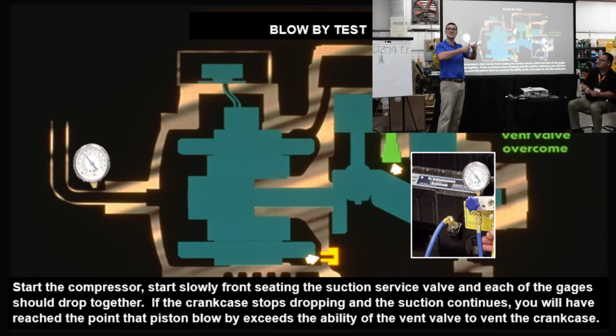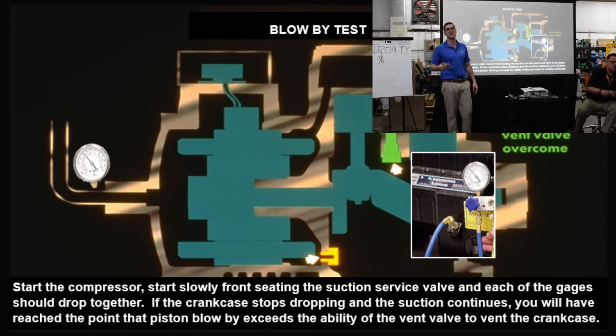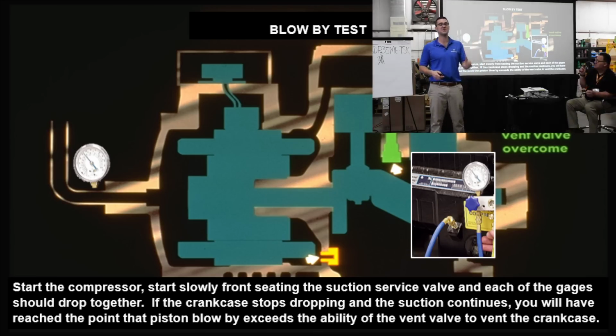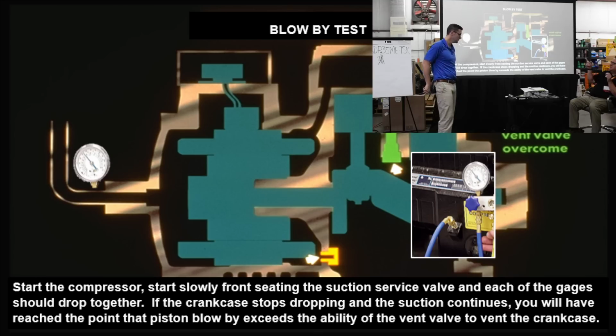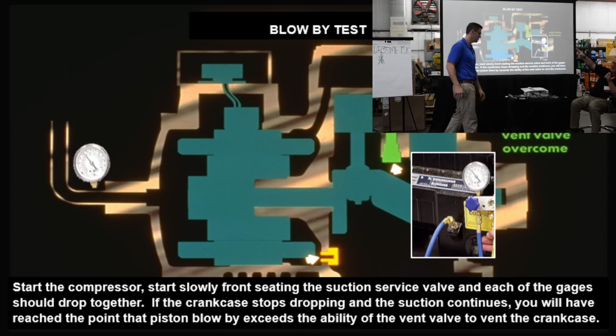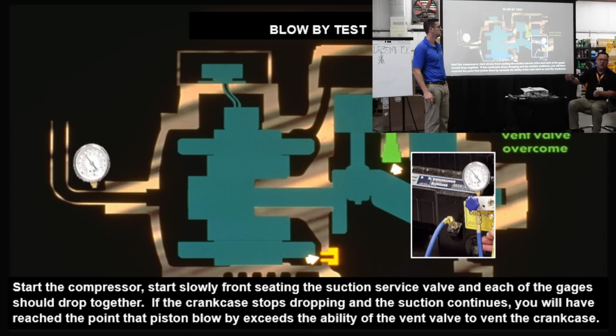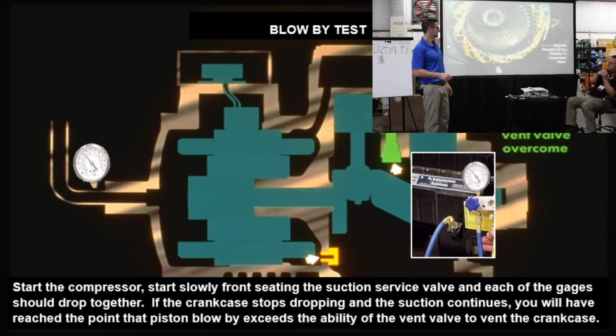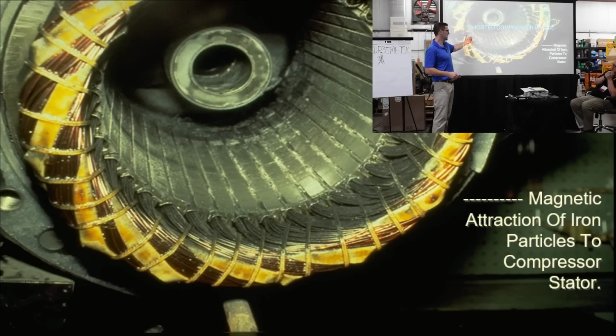Now you're wearing those cylinders, and as the compressor is pushing that discharge gas in, you come in as a nuisance trip on the Sentronic. Really, you got blow-by, the compressor needs to be replaced. And on that note, I don't want to steal Trevor's thunder, but that is the thinnest film of oil in the whole compressor, between the piston and the cylinder. And then overheat causes shorted motors, with no lubrication in that stator and that rotor.